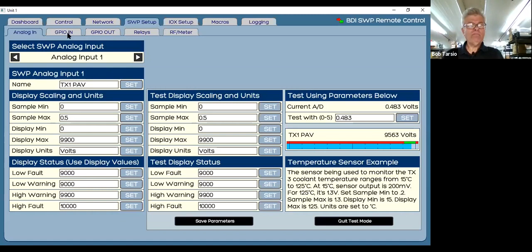Remember the days when you'd put the sample on there and say, I want it to read 9,000 volts, then you test it and a voice would say the voltage is 8,500 volts, and you'd have to play with it more to get it right? You don't have to do that anymore. You just put the voltage in here, set it for what you want, and you're done. You do that on every input, you can name it, and you're finished.